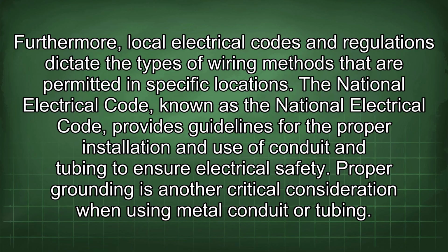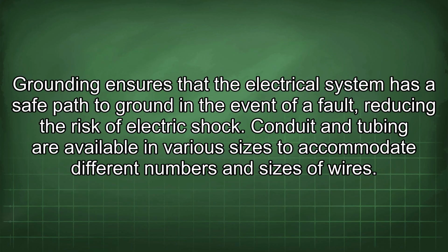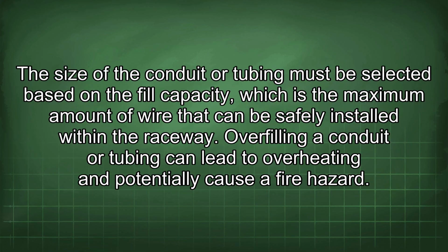Proper grounding is another critical consideration when using metal conduit or tubing. Grounding ensures that the electrical system has a safe path to ground in the event of a fault, reducing the risk of electric shock. Conduit and tubing are available in various sizes to accommodate different numbers and sizes of wires. The size of the conduit or tubing must be selected based on the fill capacity, which is the maximum amount of wire that can be safely installed within the raceway. Overfilling a conduit or tubing can lead to overheating and potentially cause a fire hazard.